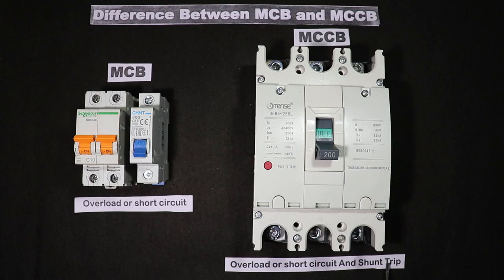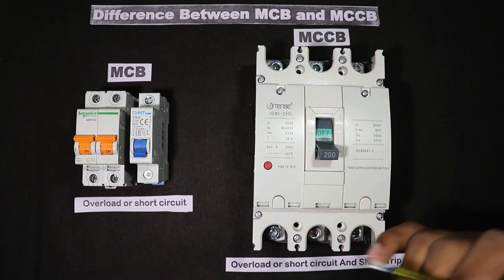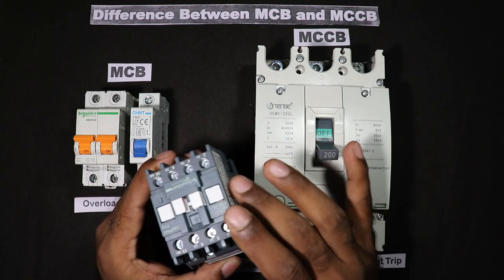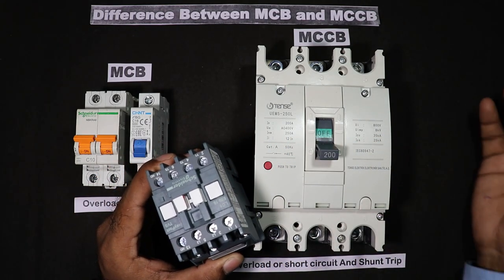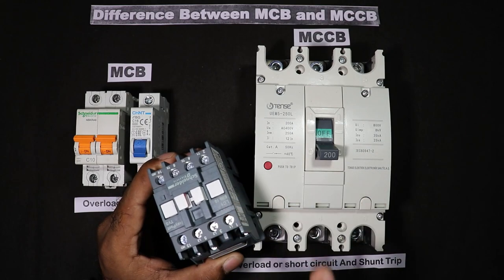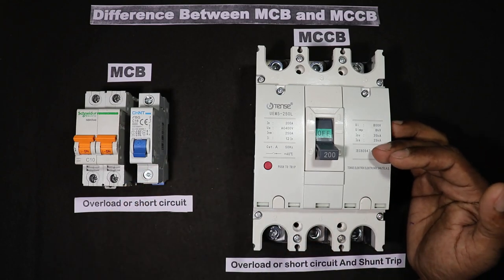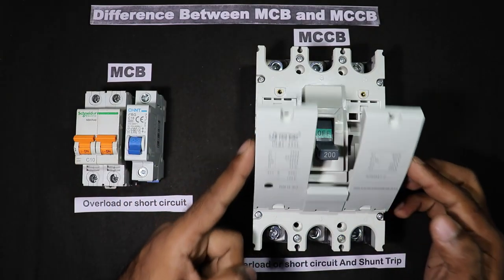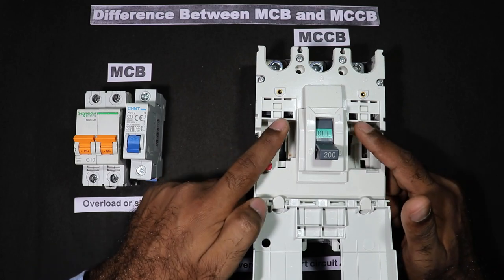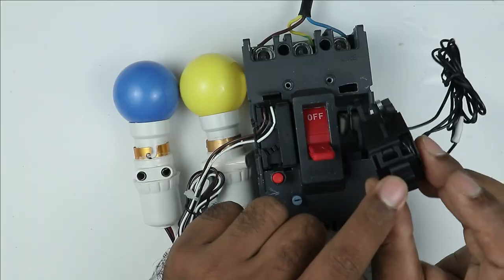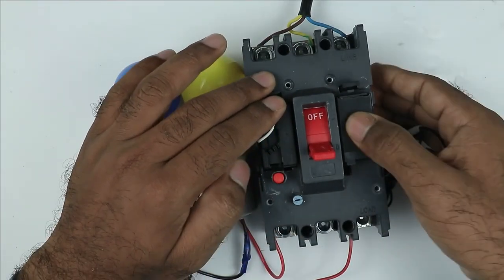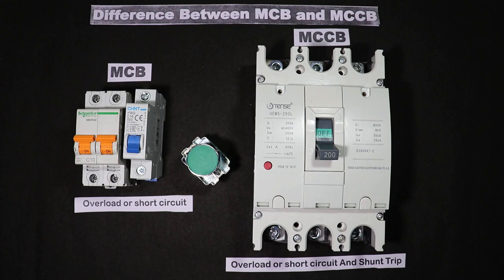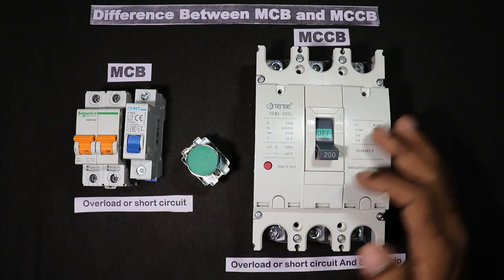Besides, shunt trip is a feature here which means we can make this MCCB trip separately. By simply pressing a push button I can let this breaker trip. As you have seen with contactors, we use interlocking so that if any problem occurs the contactor will turn off by itself. Similarly, in this MCCB a shunt is placed inside — at the back side there is an option to connect the shunt. I am opening the cover so you can see: some space is provided where you mount the shunt coil. Two wires come out which can be connected with a push button or used in any kind of interlocking. When we press the push button, this MCCB will trip instantly.